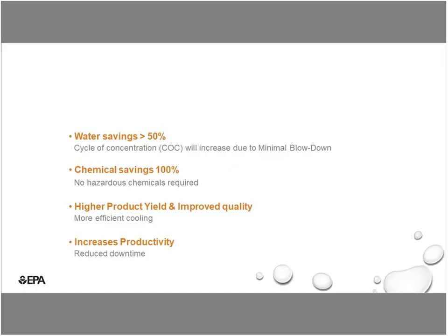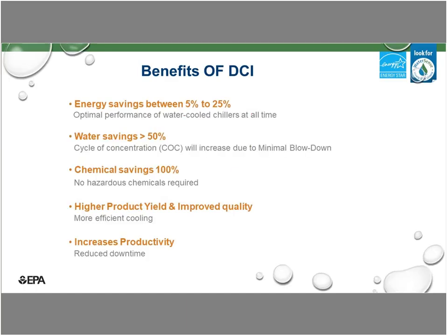So the benefits of DCI: typically we get about 5 to 25% energy saving, and anytime greater than 50% water saving. Every time we double your COC, we give you 50% water saving. If we quadruple that, we give you 75% water saving. Of course, chemical saving, you save 100%. There's no chemical required.